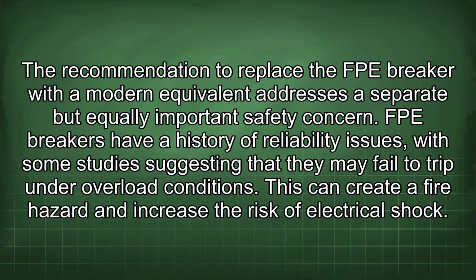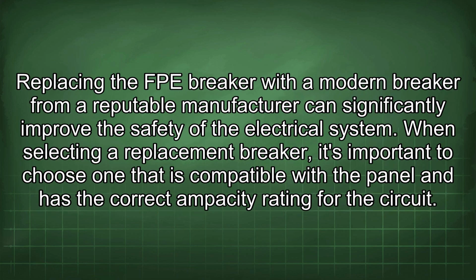The recommendation to replace the FPE breaker with a modern equivalent addresses a separate but equally important safety concern. FPE breakers have a history of reliability issues, with some studies suggesting that they may fail to trip under overload conditions. This can create a fire hazard and increase the risk of electrical shock. Replacing the FPE breaker with a modern breaker from a reputable manufacturer can significantly improve the safety of the electrical system.